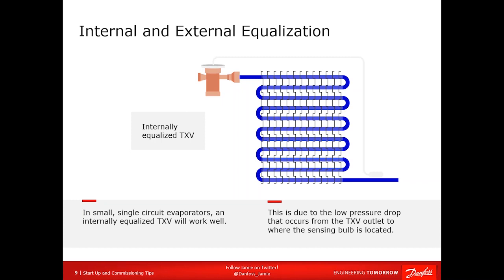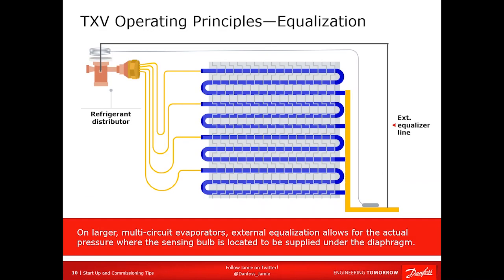You can use an internal equalized TXV, because the pressure difference between the outlet of the valve at the inlet of the evaporator and where the sensing bulb is very small. So its impact on the opening superheat of the TXV is minimal. So you're good to go. However, if you have a refrigerant distributor, you 100% absolutely need an external equalizer line.